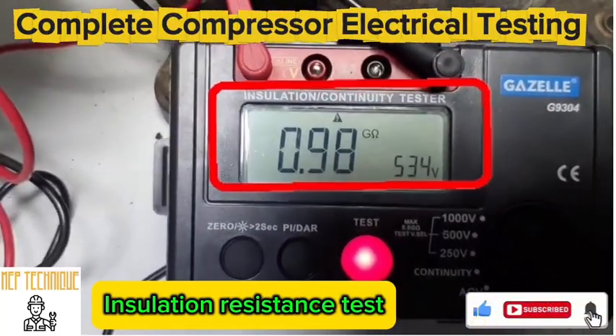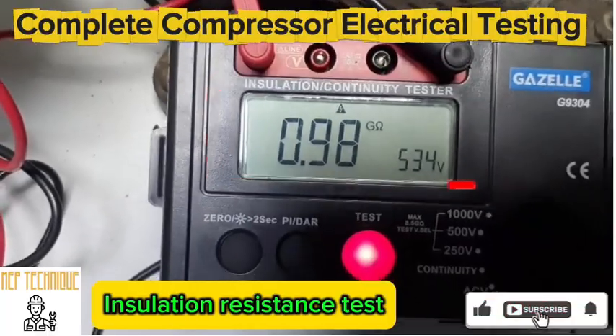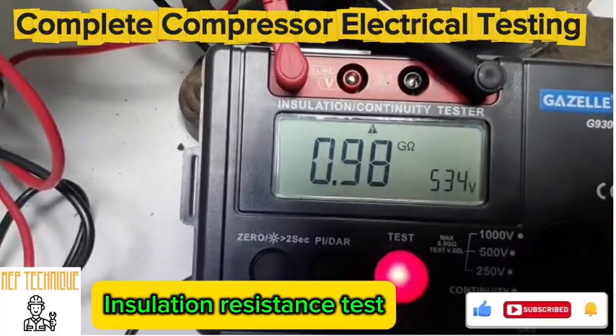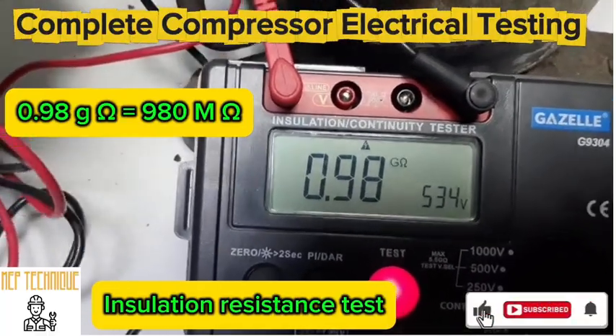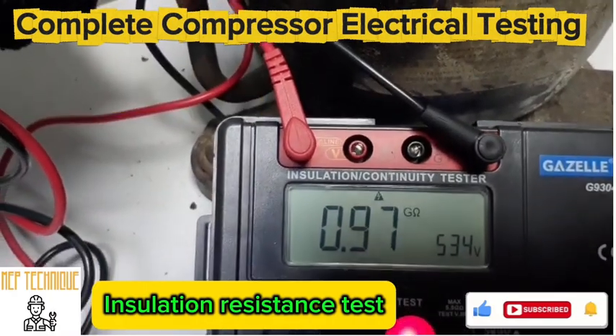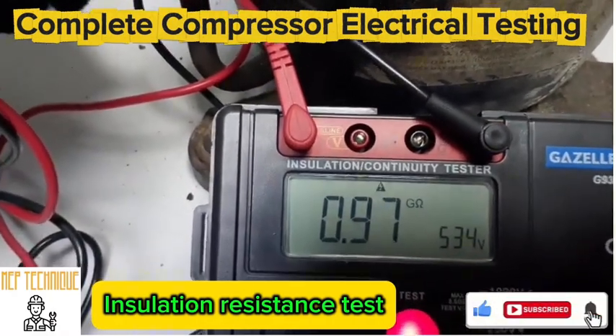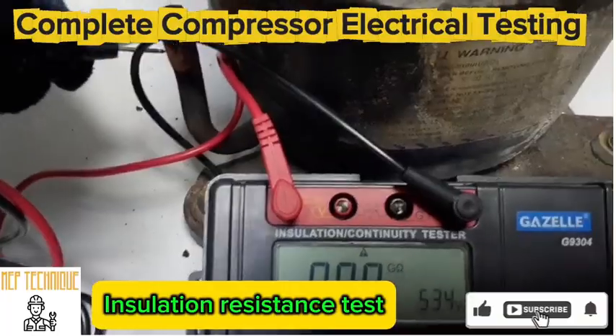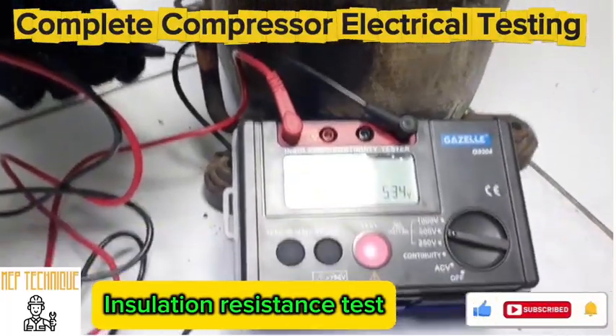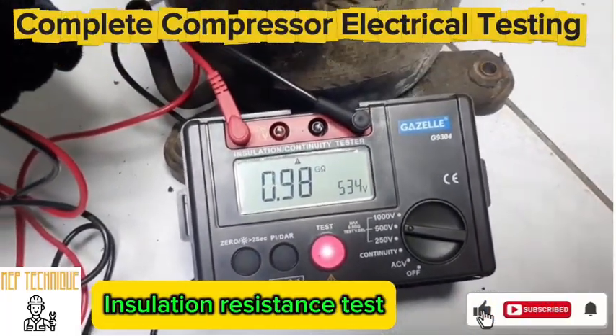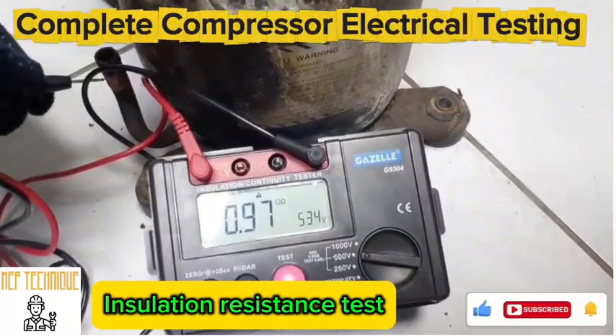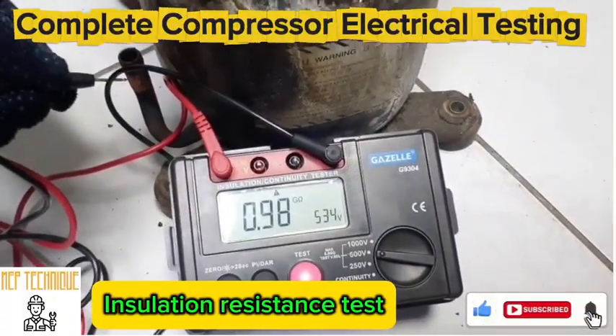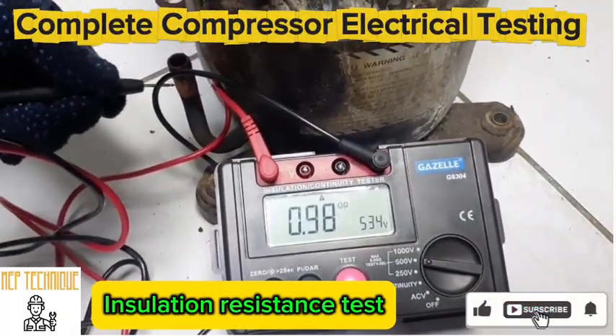1 giga ohm is equal to 1000 mega ohm, so 0.97 is equal to 970 mega ohm. That means it is not bad. Electrically this compressor is okay because the insulation shows about 970 mega ohm. If the resistance is below 2 mega ohm, then we can say the compressor is faulty.